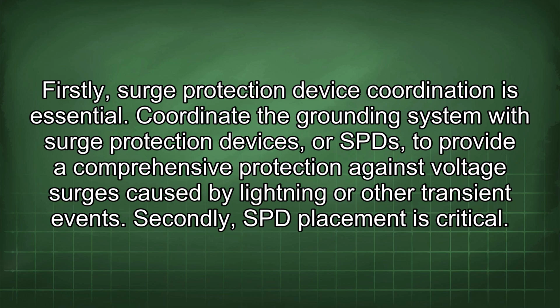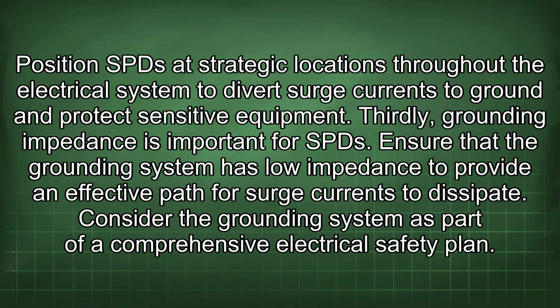Secondly, SPD placement is critical. Position SPDs at strategic locations throughout the electrical system to divert surge currents to ground and protect sensitive equipment. Thirdly, grounding impedance is important for SPDs. Ensure that the grounding system has low impedance to provide an effective path for surge currents to dissipate. Consider the grounding system as part of a comprehensive electrical safety plan.